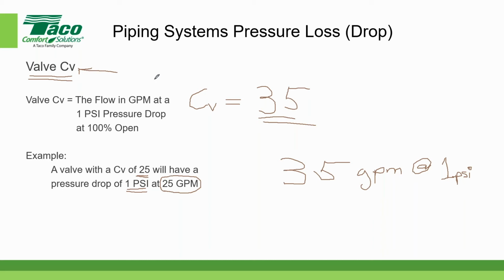And generally, it's not something you can calculate. It's something that has to be published by the manufacturer of the valve. So any questions about where CV comes from?